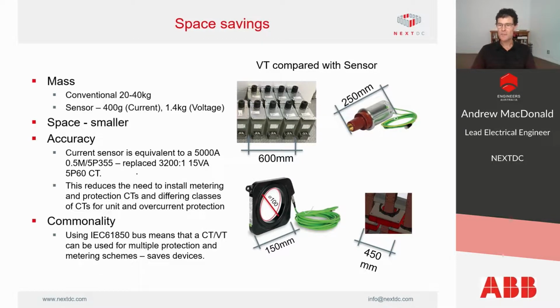Space savings. The sensors are considerably smaller and lighter than the conventional VTs and CTs. The sensors weigh 400 grams compared with the CTs, which were weighing about 38 kilos in our case, and the voltage sensor weighed about 1.4 kilos compared with about 28 kilos for the VTs we were using. They were also much smaller, which means they take up less space in the switchboard, which potentially means you can fit more of them in.